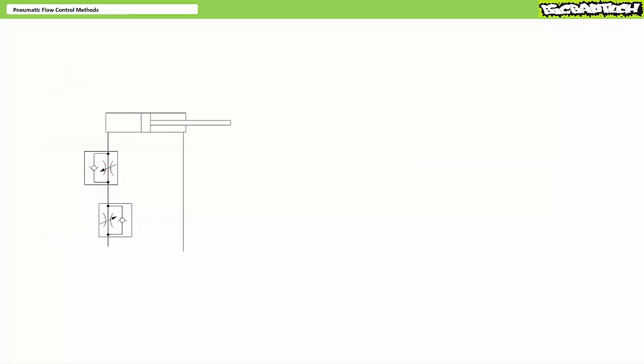Lastly, I should mention that one can use a combination of methods to control both extension and retraction. Consider one such possibility with two flow control valves with check valve bypasses both installed in the cap end of a cylinder. Flow control valve one establishes a meter in extension arrangement by forcing all flow entering the cap end during extension through the narrow restriction. During extension, flow control valve two would be bypassed. One would adjust flow control valve one to dial in extension speed.